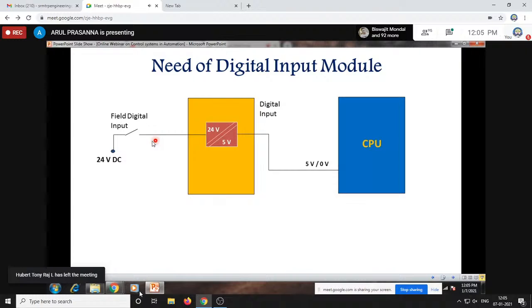When you give 24 volts at the field input device, your CPU will receive a binary value of 1. When you give 0 volts at the input, your CPU will receive a binary value of 0. In between, there is a conversion from 24 volt to 5 volt. The similar thing happens in your output module also.